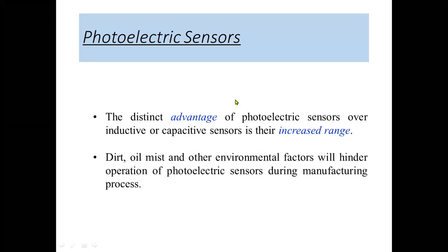The advantage of photoelectric sensors over inductive or capacitive sensors is their increased range. Dirt, oil mist, and other environmental factors will hinder the operation of these photoelectric sensors during the manufacturing process. But again, the advantage of photoelectric sensors compared to inductive or capacitive sensors is the increased range.